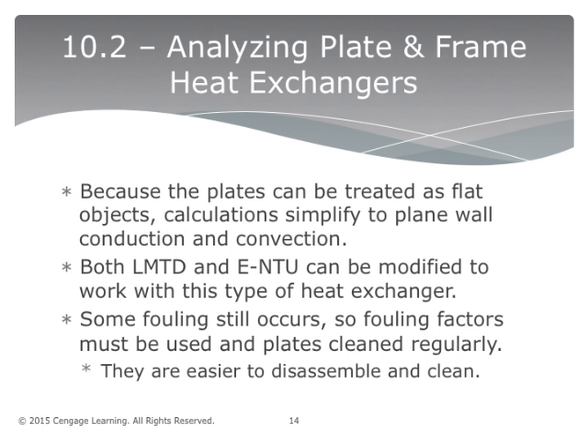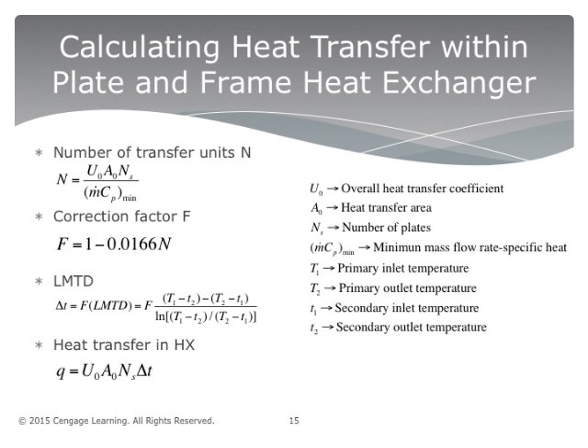Plate and frame heat exchangers have large conductance coefficients, up to 6,000 watts per meter squared Kelvin, for liquid-to-liquid use. They are ideally suited for low viscosity fluids. The projected area of plates is usually taken as the nominal heat transfer area, in spite of the real curved surfaces and lost space in gaskets and ports. The major limitations in plate and frame heat exchangers are maximum allowed pressure, usually below 1 megapascal, and the temperature range, which is usually limited to 150 degrees Celsius.